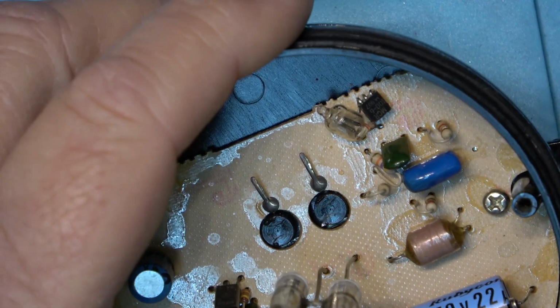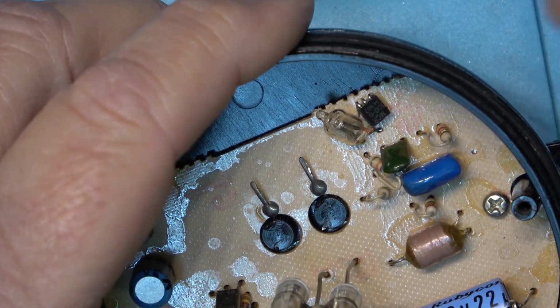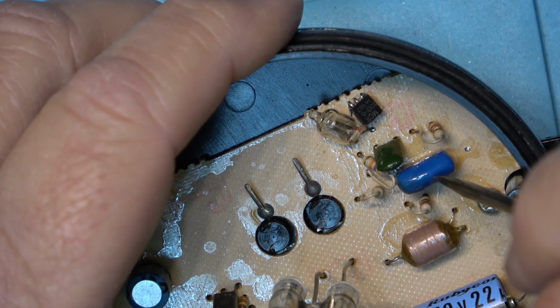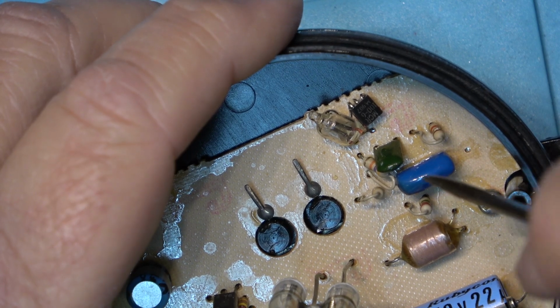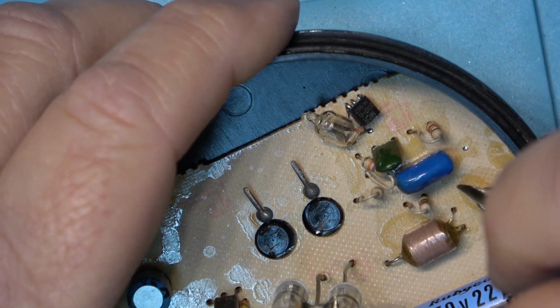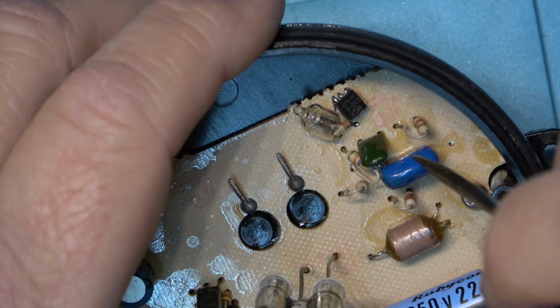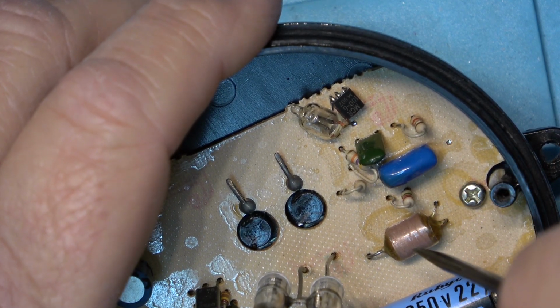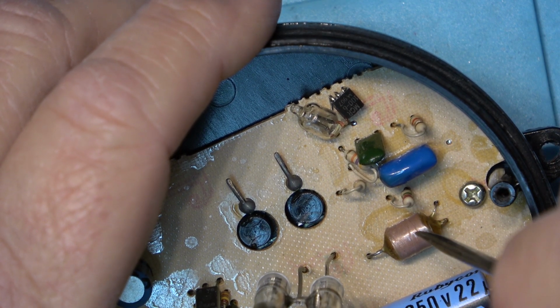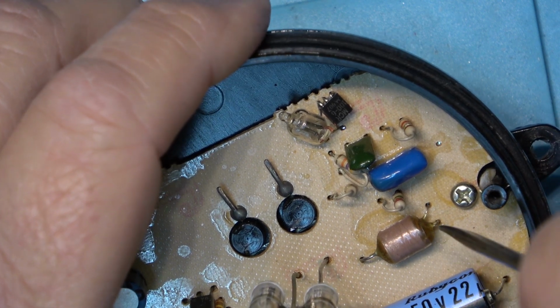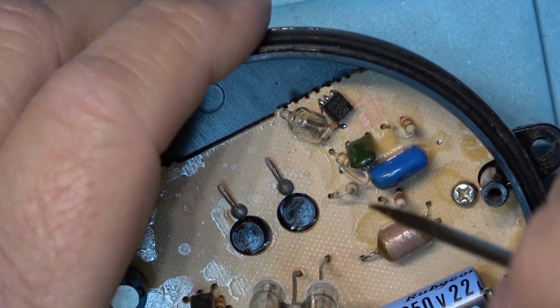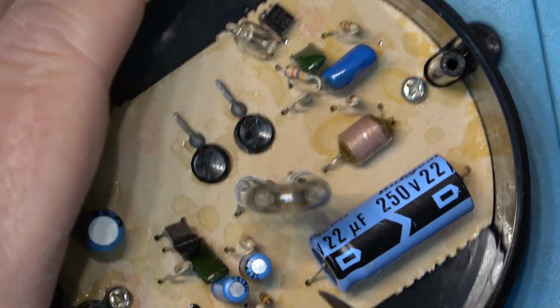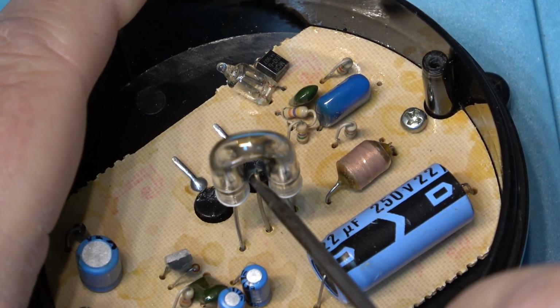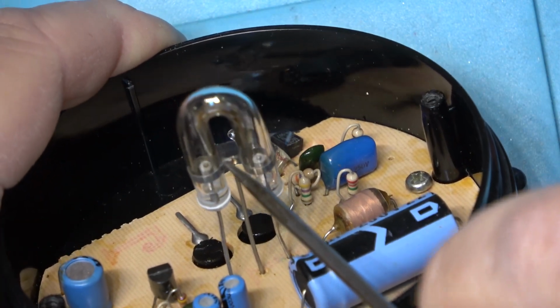Actually, you have two capacitors. One is going to charge, that's this one here. This one charges up as well. This is your kicker, which discharges into the little transformer, a step-up transformer that generates probably around 4 kilovolts of pulse, which is applied to the trigger electrode.